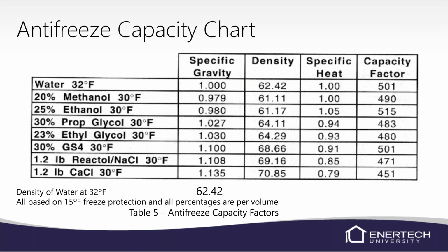Antifreeze capacities, I'm not really going to get into this a whole lot, but they will give you the exact capacity factor or your brine factor over here to the right for every single one. You'll see 30% propylene glycol is 483, so only 2 points off of the 485 that we normally use. And you can see methanol's got 490. If you really wanted to use the exact calculation or the capacity brine factor, you could definitely pull up this chart and use it. But for our sake and simple calculations, we just use the 500 for water and 485 for an antifreeze mixture.